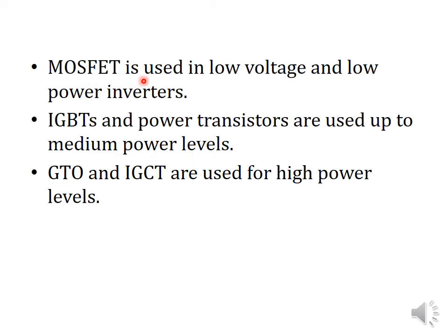MOSFET is used in low voltage and low power inverters. IGBT and power transistors are used up to medium power levels. GTO and IGCT are used for high power levels.